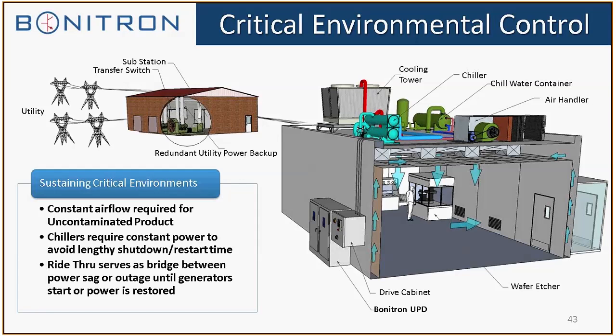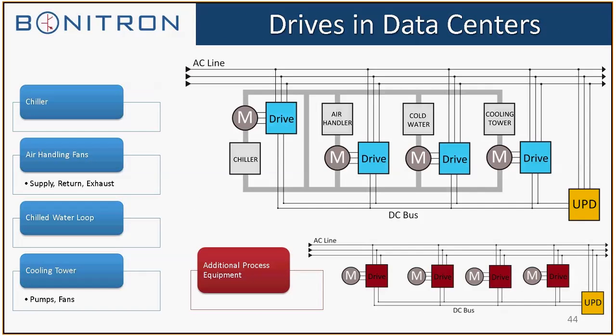And this just shows a clean room. And here is a pretty much standard chill water system. Data centers, anywhere you're gonna find this type of a lineup. And this is a good application for common busing several drives on one UPD. You can cover the air handlers, the chill water, cooling tower, all on the same DC bus. You size the ride through to cover all of them.